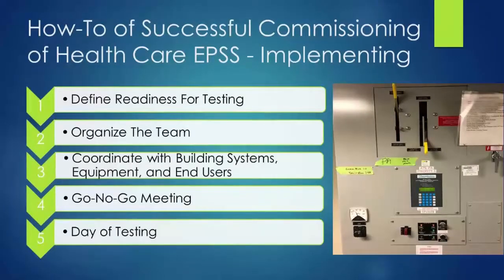So how do we observe and watch all of these? What we ended up doing is placing an electrical contractor and electrical maintenance staff in each space. In the picture, you see an ATS on a project — we put tape on the face of each ATS that was going to be operated, labeled with which test and step it would operate under, and gave the local contractor and maintenance staff two-way radios. We communicated clearly with everyone on when to report back and what they should be watching for. That took some time to organize everybody on what they were going to do.